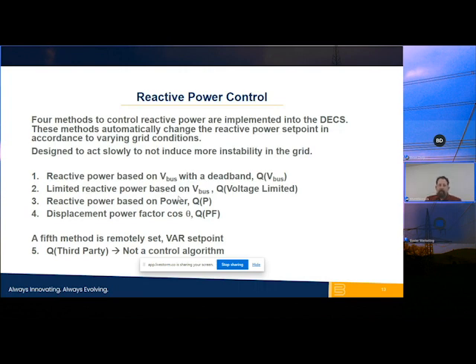And then the final one is the displacement power factor method. It's somewhat similar to modes 2 and 3, but now we're looking at the grid power factor component. So we're maintaining a fixed power factor at the grid connection. It's not exactly the same as the internal power factor mode that is included in the DECS products. This is again a slower algorithm that's on top of it, but what it's doing is maintaining the power factor at that grid point.